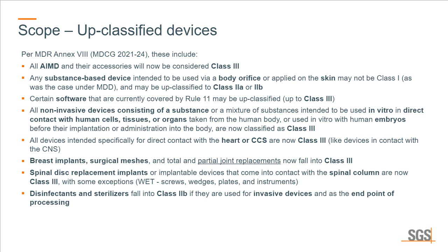Some of these devices were already class 3 before, but now the range has been extended under MDR. Spinal disc replacement implants or implantable devices that come into contact with the spinal column are now class 3, with some exceptions. We are going to talk about the well-established technologies later.